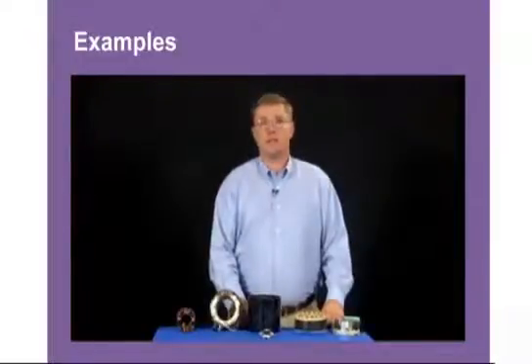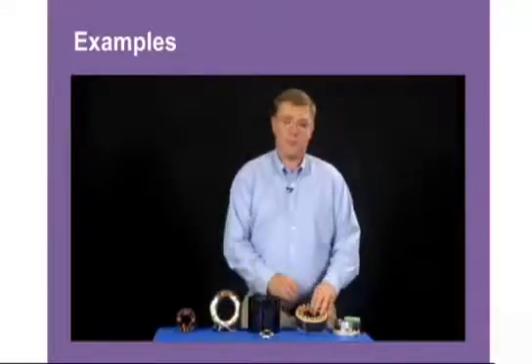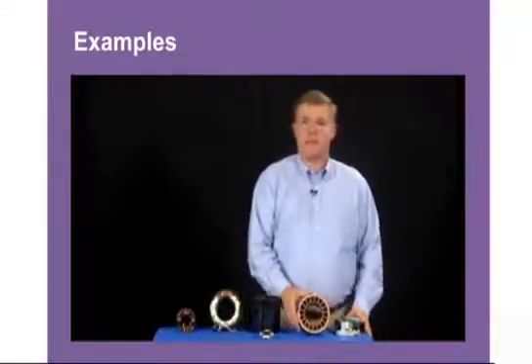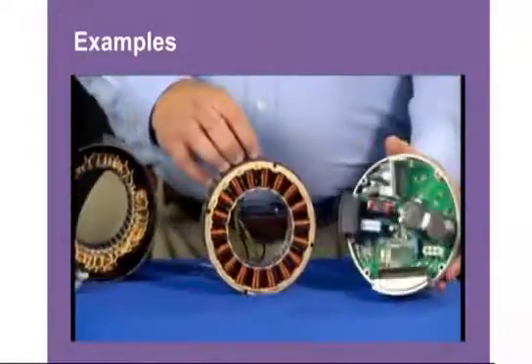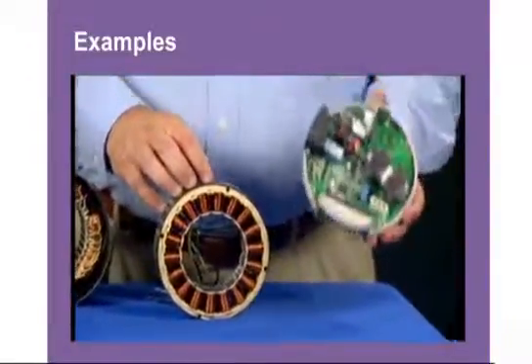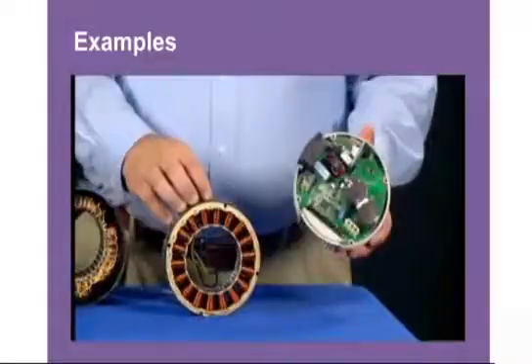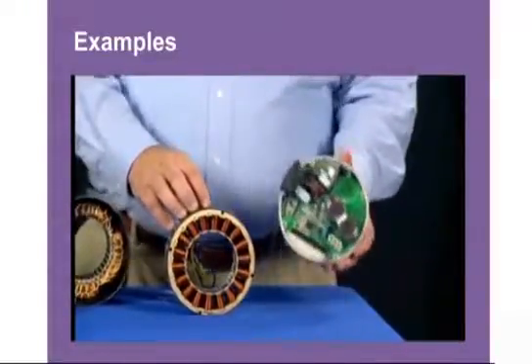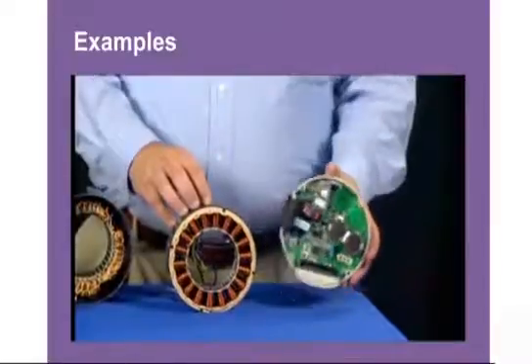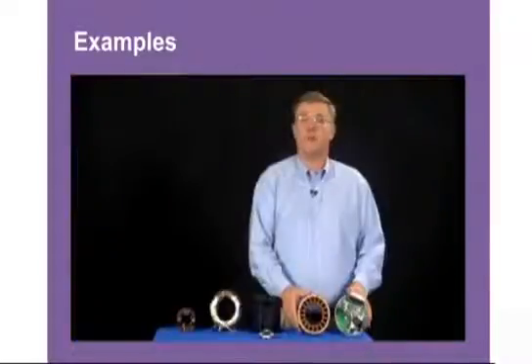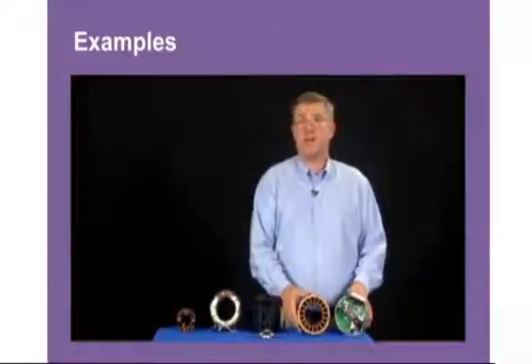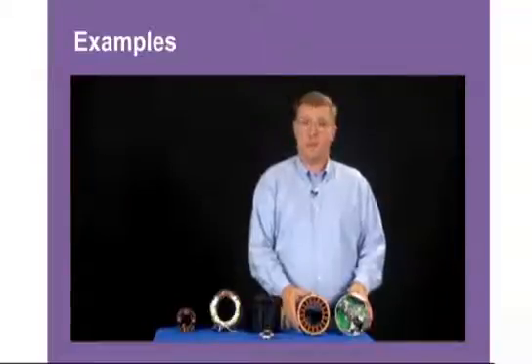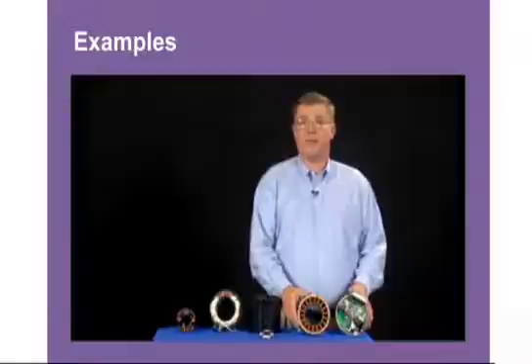The final type of motor is an electronically commutated, or ECM, motor. These type of motors are permanent magnet DC motors that have a control board that runs the motor. They are more efficient in HVAC applications and typically a good retrofit upgrade replacement for a permanent split capacitor motor. An original equipment manufacturer, or OEM, ECM motor is typically proprietary on the control board to the programming, meaning OEM ECM motors typically need to be replaced by an OEM ECM motor.